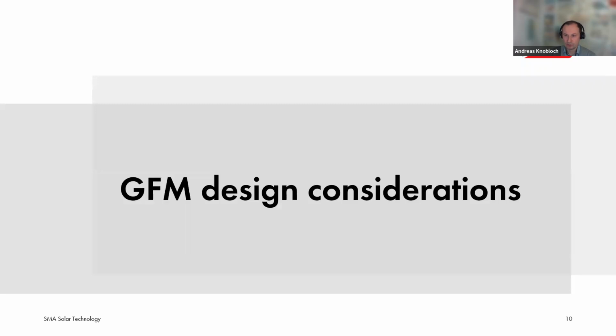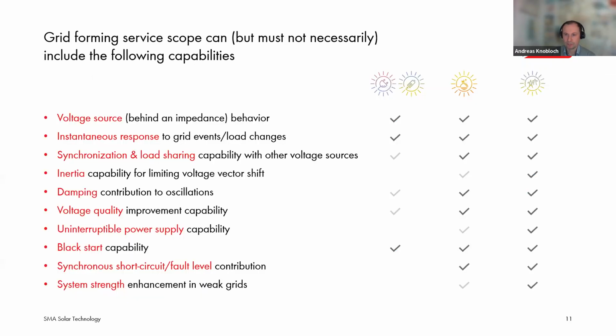Now looking into the design considerations regarding grid forming design. So what is grid forming? From our perspective, grid forming incorporates the grid forming services that can be provided, but do not necessarily have to be provided, by inverter-based resources like PV power plants or wind power plants. And this can include the following capabilities. First of all, a voltage source behavior. So someone needs to provide the voltage reference and the angle reference for grid following sources and also grid following loads and grid following storage.